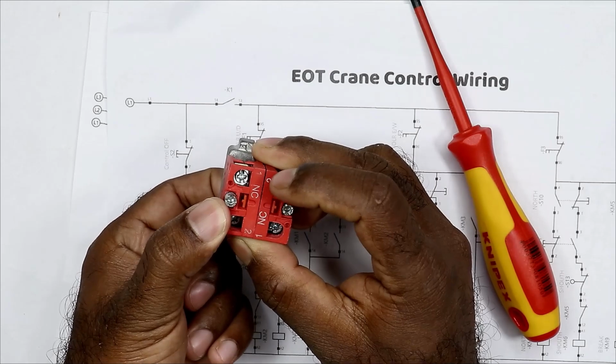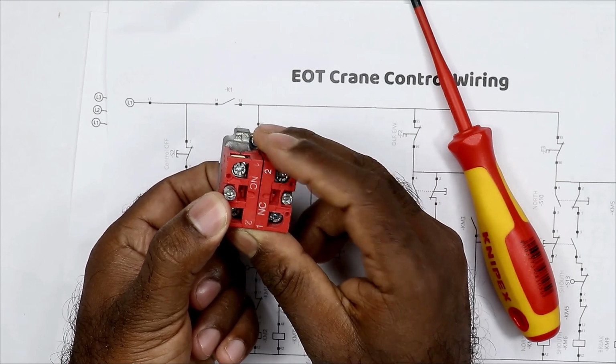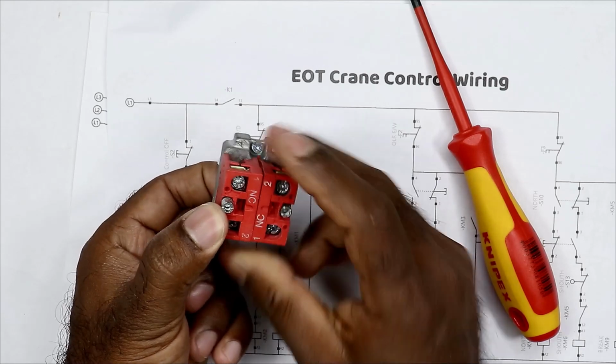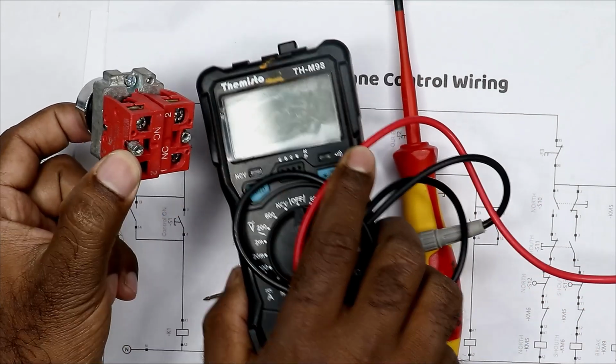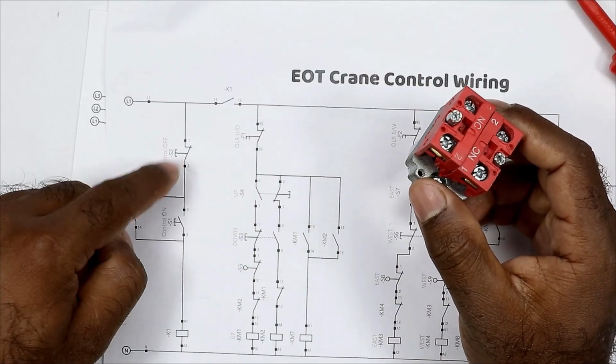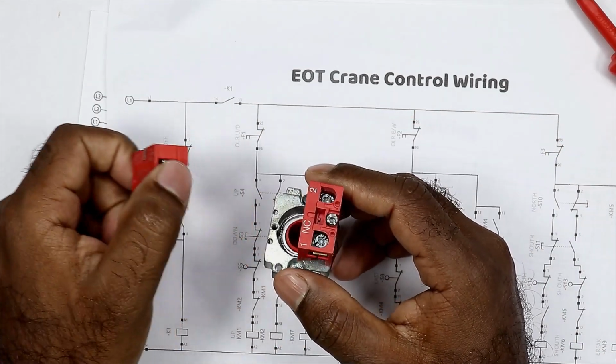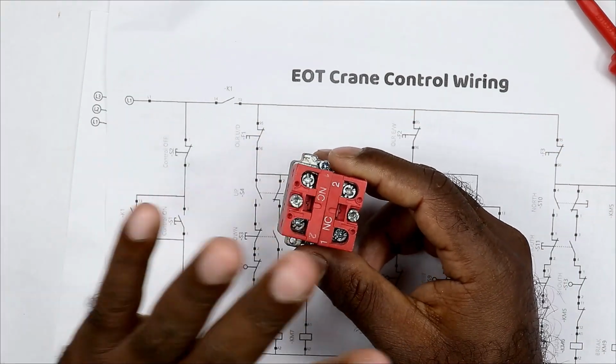Due to the movement, the contact inside of this changes. Whether the contact is changing or not, we have to check this. For checking, you can simply use this type of multimeter. If the wire connections are alright here, then it is possible that the element is faulty. So first of all, change the element, and after this, make the same connection as before.